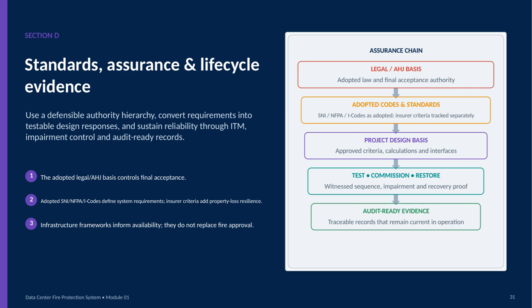The assurance chain continues through witness testing, commissioning, impairment control, and restoration. We need proof not only that the system works initially, but also that it can be safely managed when part of it is unavailable and reliably returned to service. Finally, every step should produce traceable, current, audit-ready records.